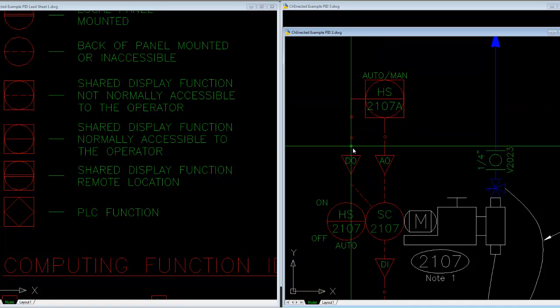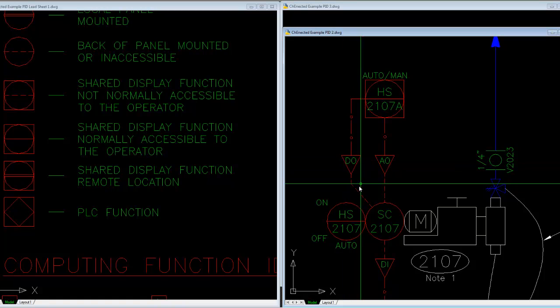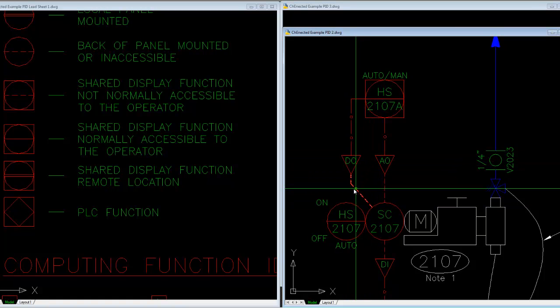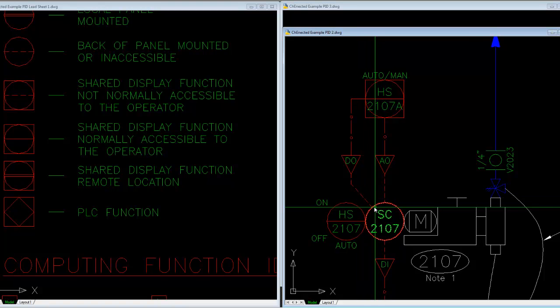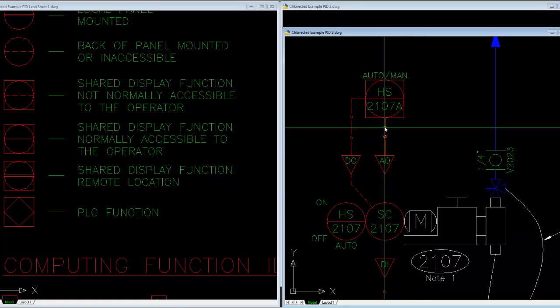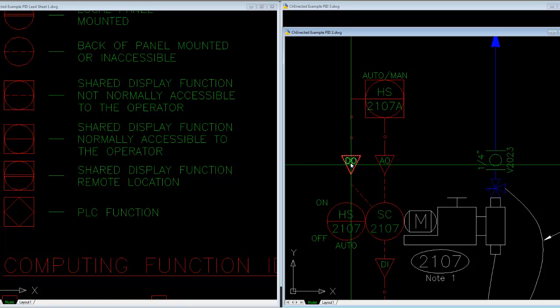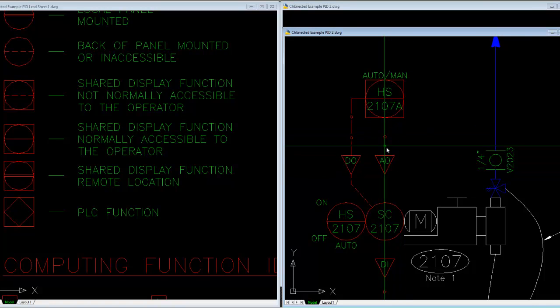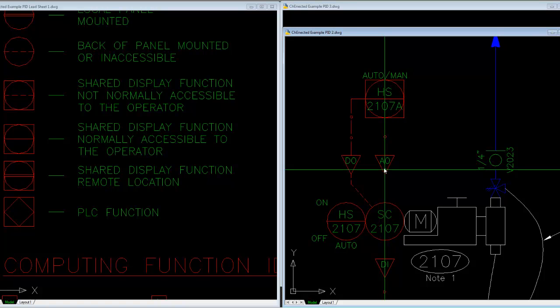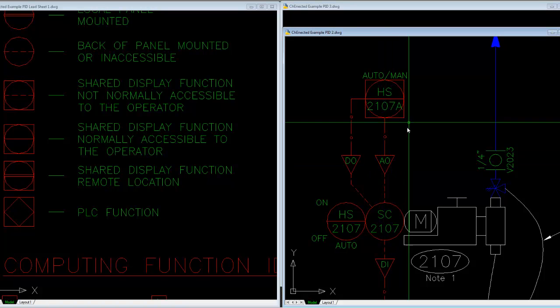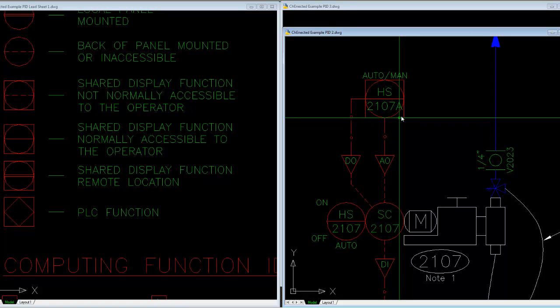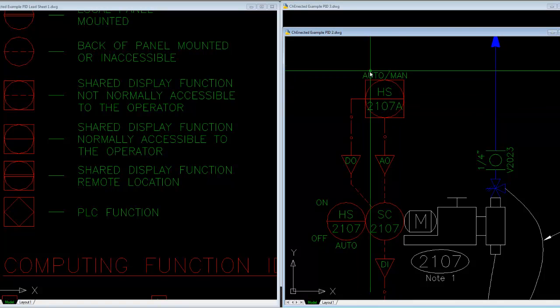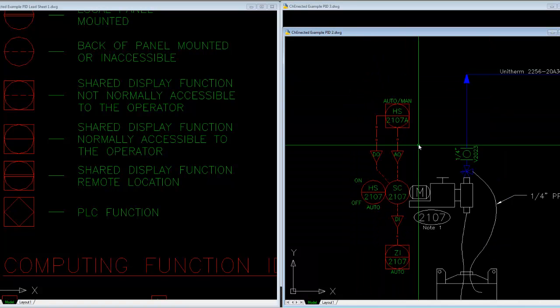It's not hard to understand: you click a button, some software program runs in the HMI, it says 'he clicked start pump,' sends a signal to the PLC, sends an output to start that pump. That signal then goes from software to electrical — a switch closes, power is supplied to that contact, and the pump starts and runs. That's a discrete, digital example — it has two states, on or off. The second would be how fast you want to run it: an analog output, rating the pump from zero to one hundred percent speed. On the HMI it might be a slider, or it may be rate-driven based on flow if it's injecting chemical on a concentration basis — that would be the auto functionality.